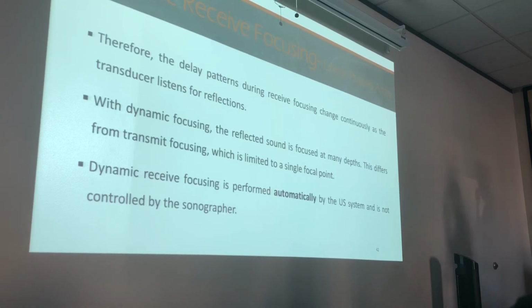With dynamic focusing, the reflected sound is focused at many depths. This differs from transmit focusing, which is limited to a single focal point, right? Because our transmit focusing just has a waist. Then we have another focal zone at another depth, creating another waist.